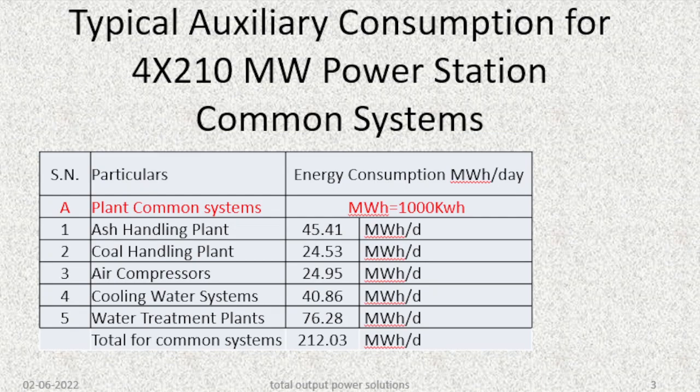The table shows a typical auxiliary consumption for a 4 x 210 MW power plant common systems. The power plant common systems are generally ash handling plant, coal handling plant, air compressors, cooling water systems, and water treatment plants. The energy consumption for each of these is mentioned in the table. The total energy consumption for all common systems is around 212.03 MWh per day.